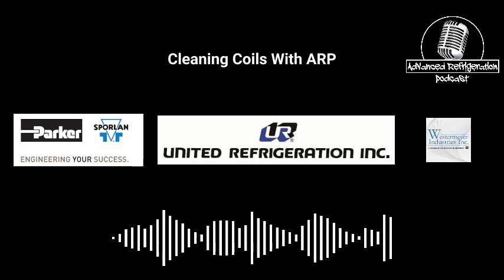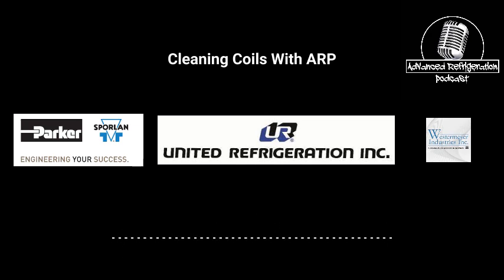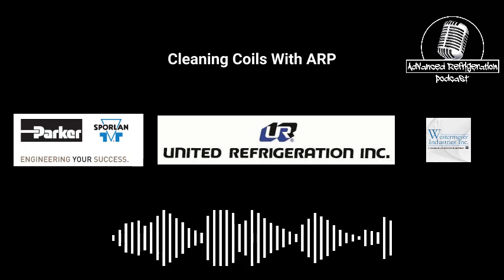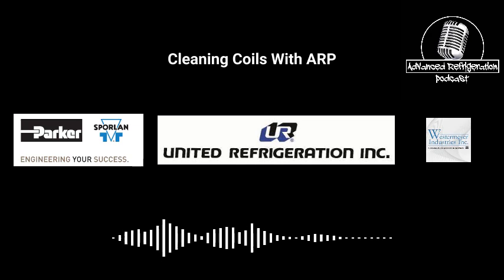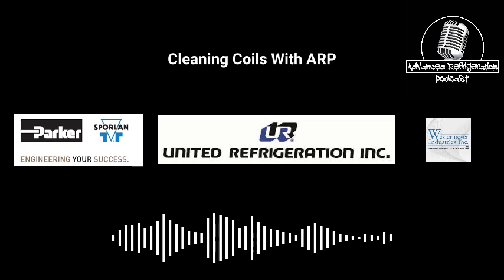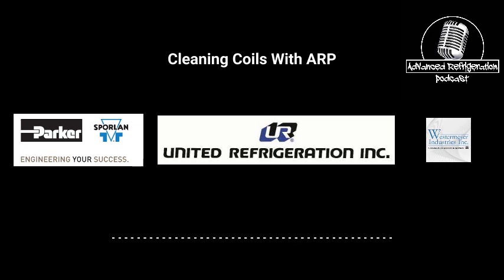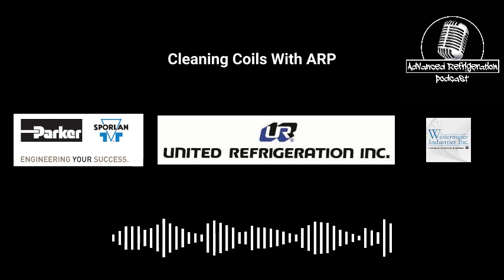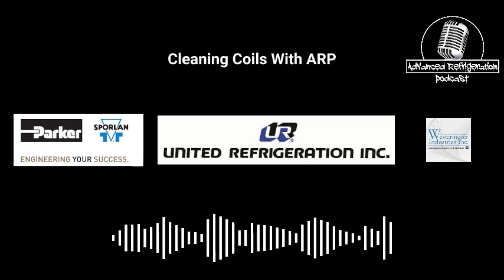So if it's just blocked up with cottonwood, all you need to do is brush it off with a pool brush. In one sweep of the pool brush, you could do about half of a fan square. So it's two sweeps of the pool brush and each fan square is done. Relatively quick, you can knock all the cottonwood off there. But if it's dirty and all nasty, you're going to have to wash it. Get the hose out and just clean it off. It doesn't take that long with the hose. Spray it on an angle, get the debris off the fins, so that you have a nice clean coil.